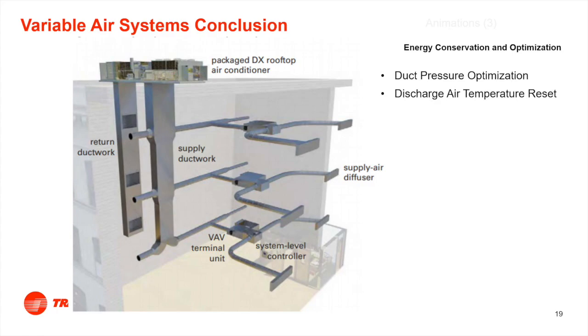Discharge air temperature reset, now think about this. This air handler was created for the hottest day of the year, 2% is what it was created for. The rest of the time, we don't need that much capacity, do we? We have the ability to use that data now to turn that equipment down.